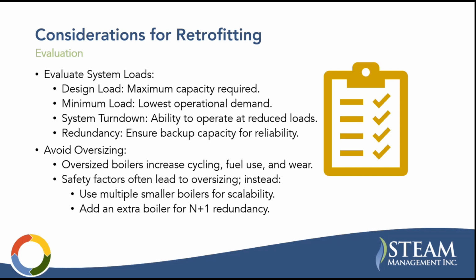Its motor stops and starts. It's thermal stresses on the boiler. So, you want to minimize cycling as much as possible. Also, consider that capacity safety factors often lead to oversizing. So you will come up with a building load.